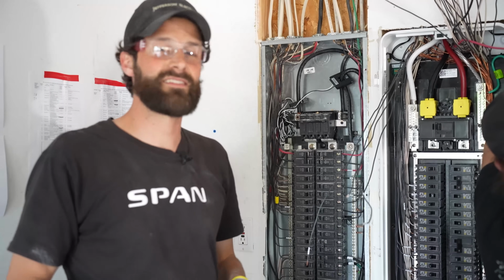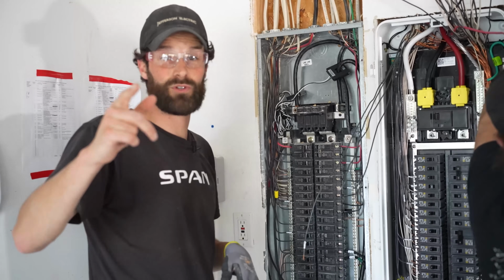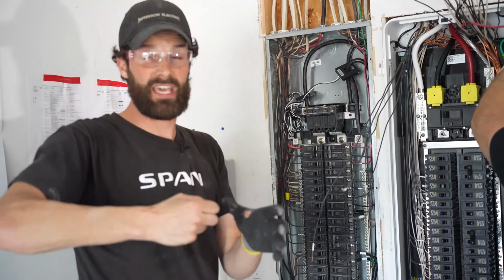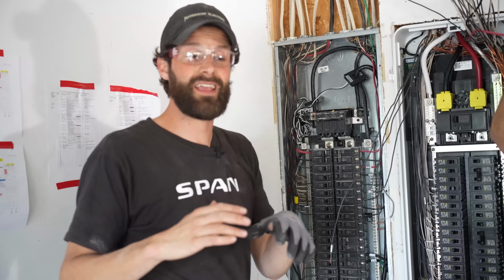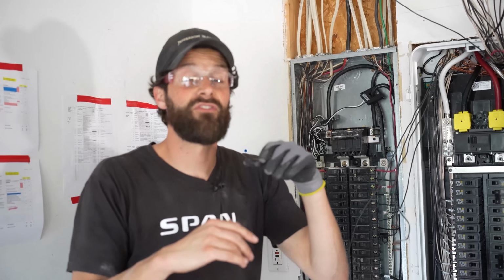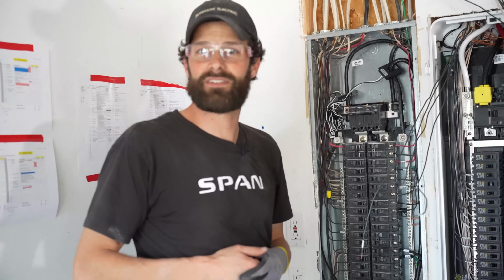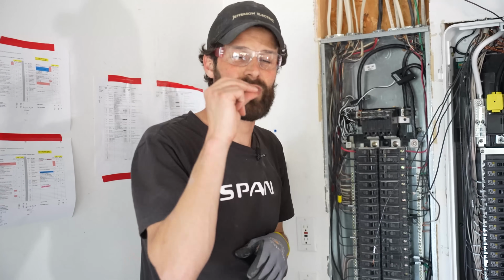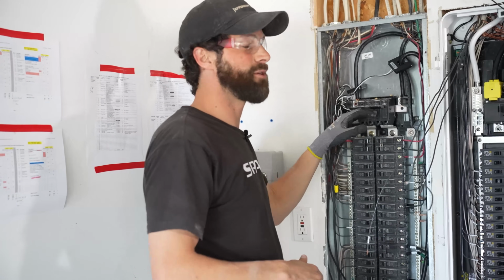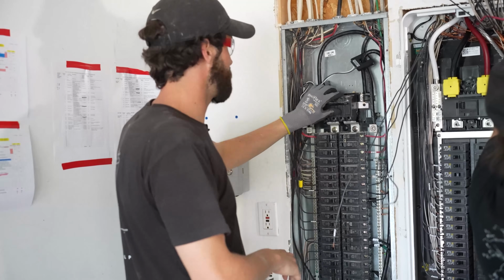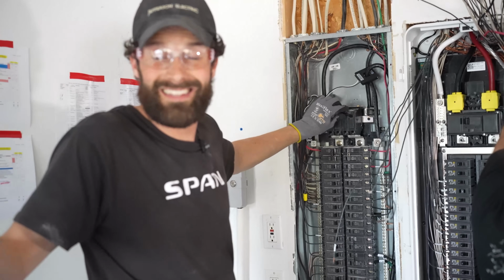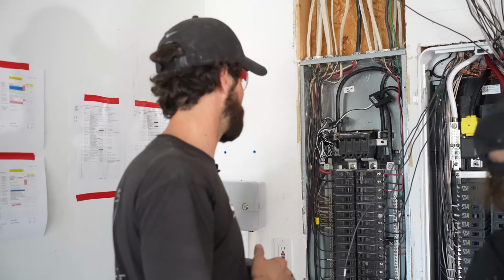would put stress on the system and is not ideal, particularly in commercial environments where you've got motor loads that'll just kick on real hard. Motor loads are insane. A 15 amp motor might have a 45 amp startup inrush current. That's crazy. So what if you had 5 15 amp motors that could operate simultaneously under normal conditions? If you trigger an event to cause them all to come up simultaneously, then you're going to kick your main, overload your system. So breakers off, main is on. Always look away just in case there's an arc flash and bits and pieces go flying.